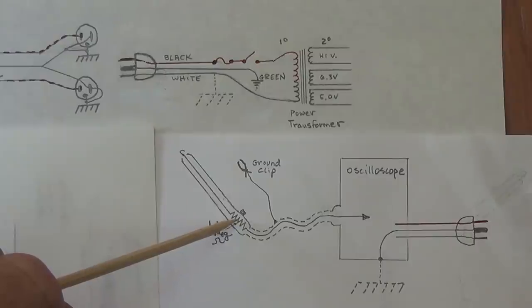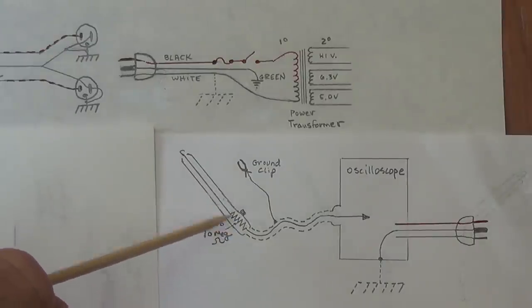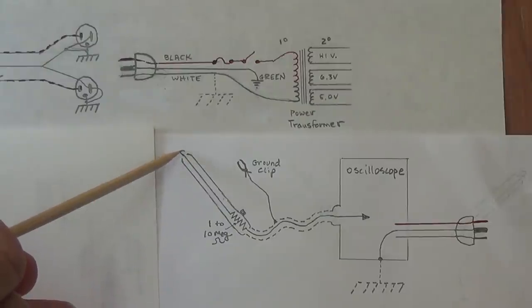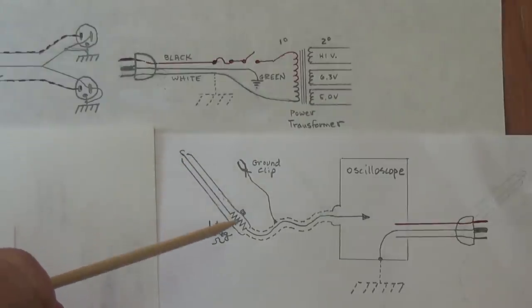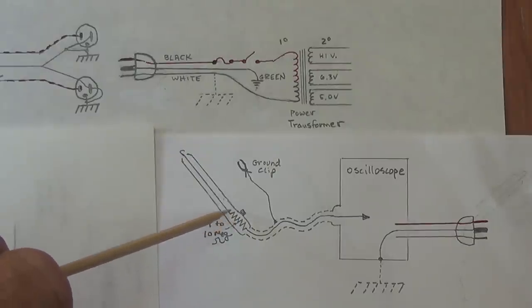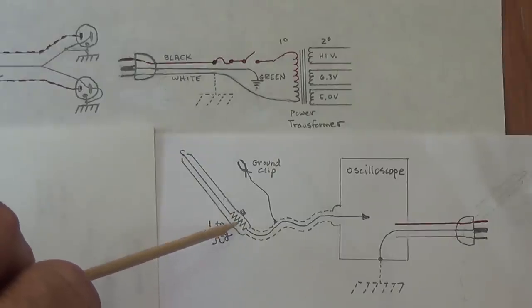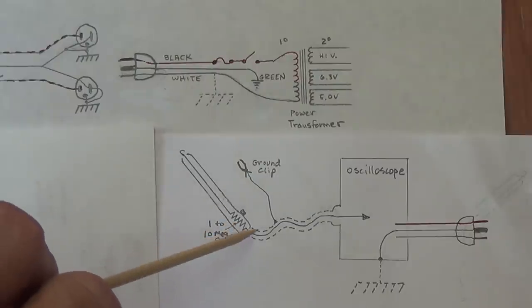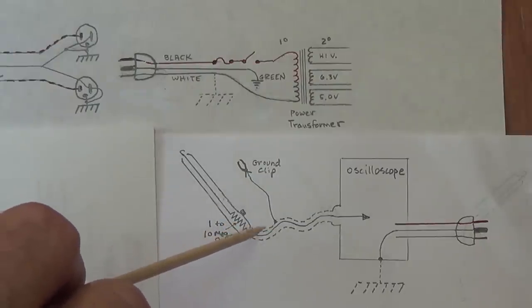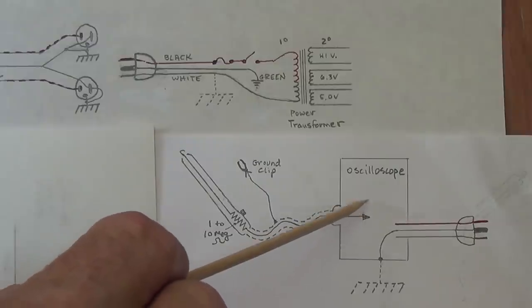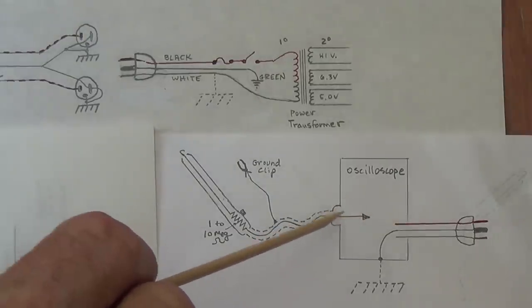This then is the buffer that pretty well protects us from harming our oscilloscope by touching the lead here to a high voltage spot. You still have to be careful, but this resistance reduces the chances of harming the instrument. We see that that hot wire comes in here and goes into the circuitry of the oscilloscope.